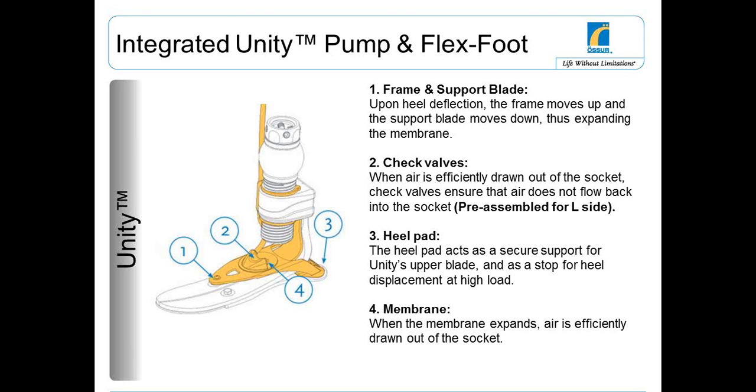The membrane itself is removable from the bottom, so if you ever had a membrane that failed, you can replace that as well, all in the same unit. We have been informed from America that they haven't had a single support blade break yet. They've been working with this system for about a year now, and they haven't had any failures, which is really great news. So we feel pretty confident with the reliability of this system.